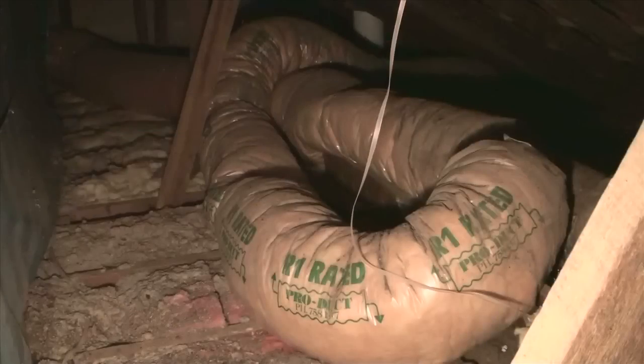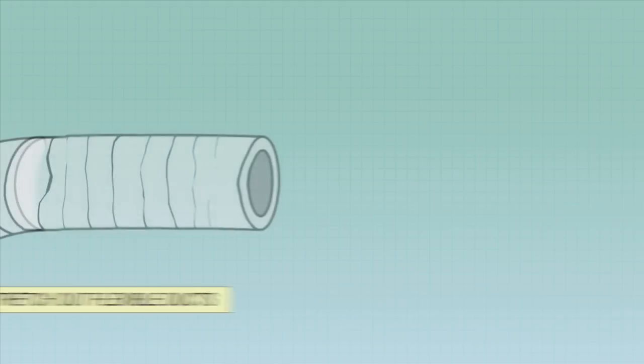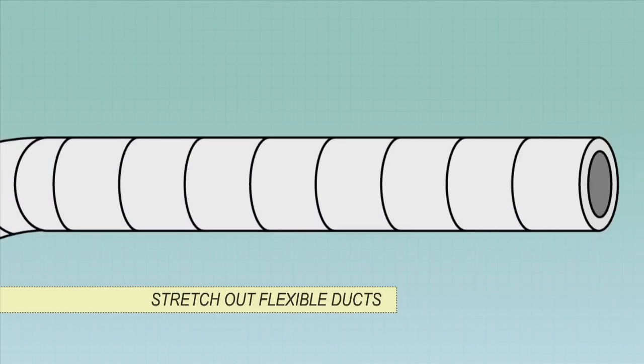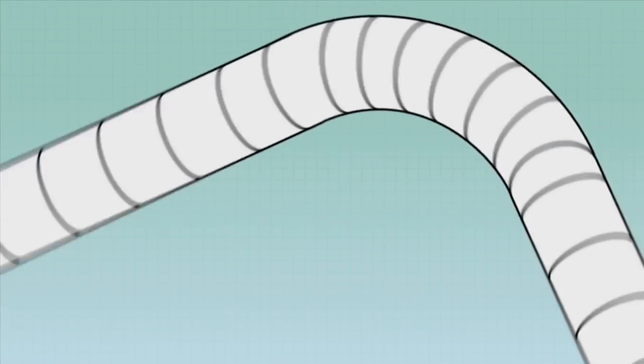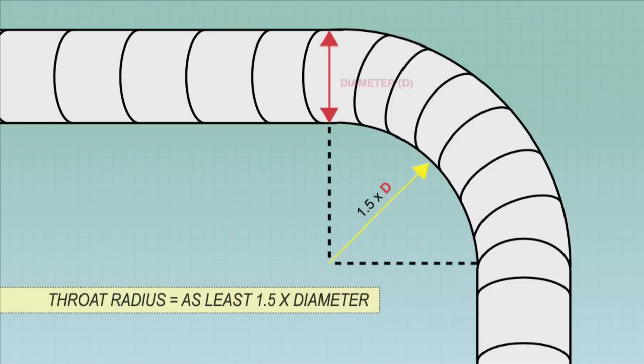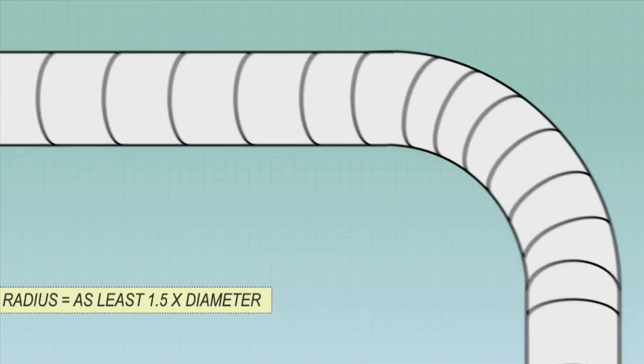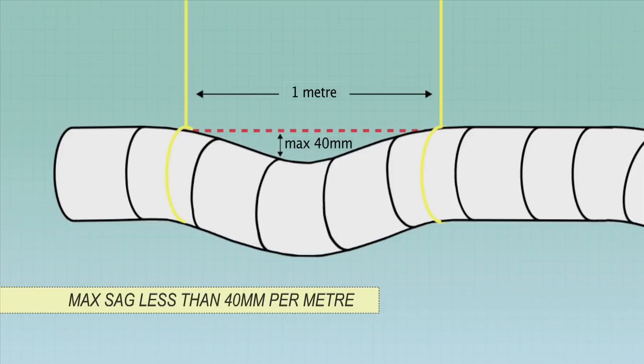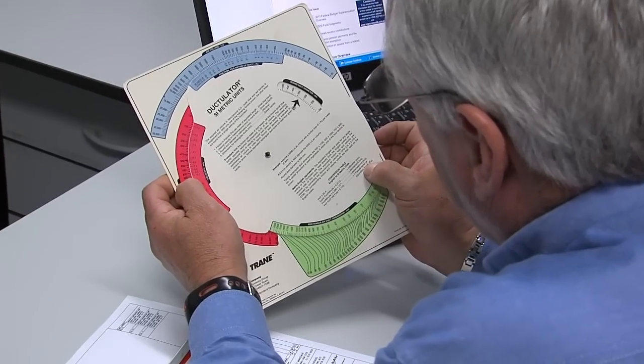Poor ducting can waste a lot of energy. Make sure you follow the Australian Standards and the Building Code of Australia when installing ducting. To minimise flow resistance, stretch out flexible ducts and don't bend them unnecessarily. 90 degree bends must have a throat radius of at least 1.5 times the diameter of the duct. Duct work must be supported every 1.5 metres, and the maximum sag between supports must be less than 40 millimetres per metre. Duct sizing is crucial, so use a ductulator to size each duct.